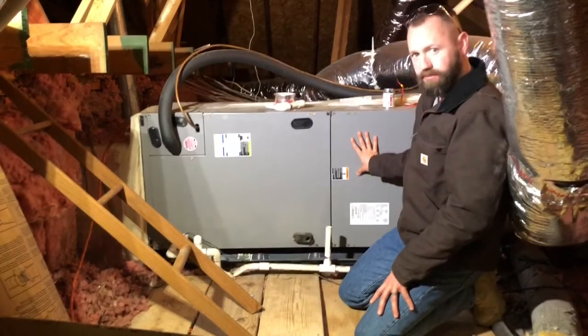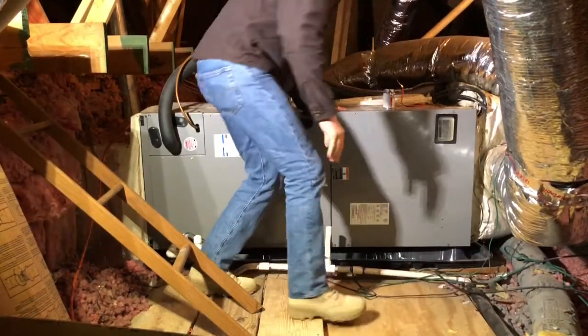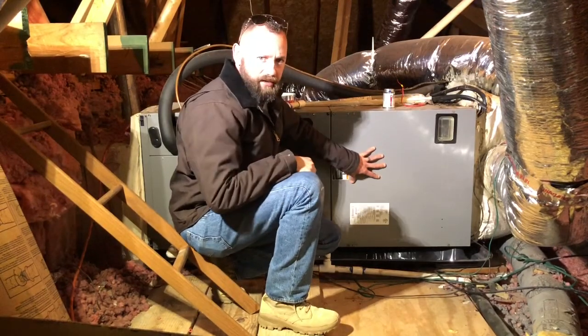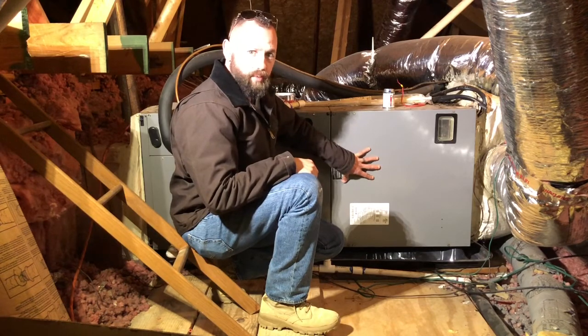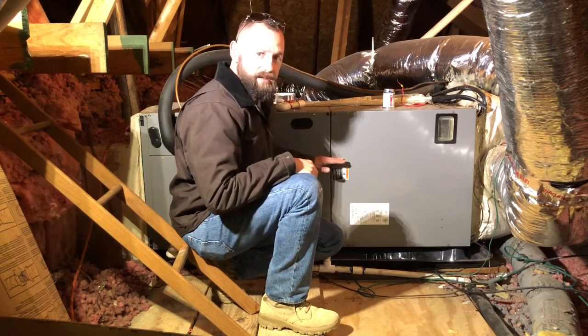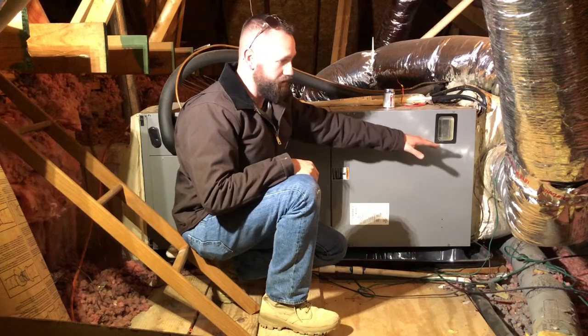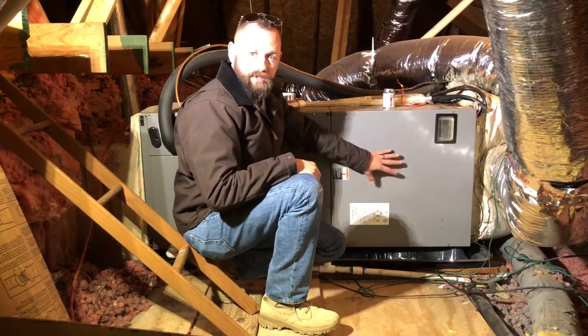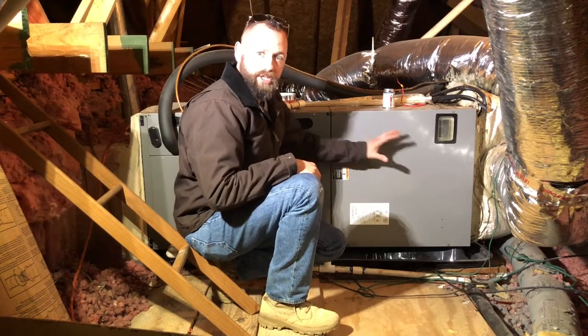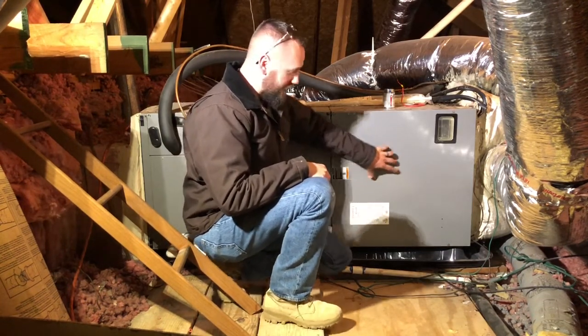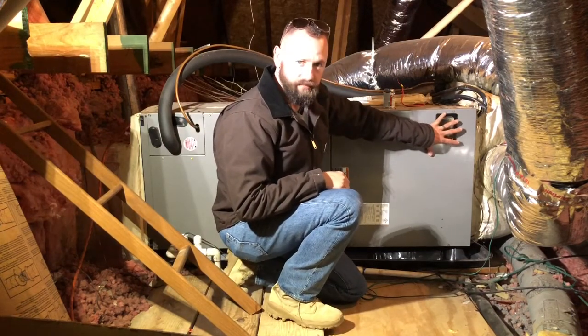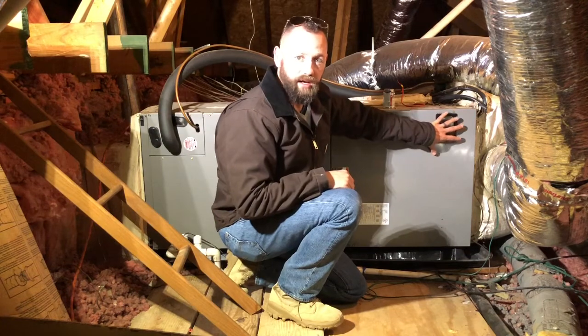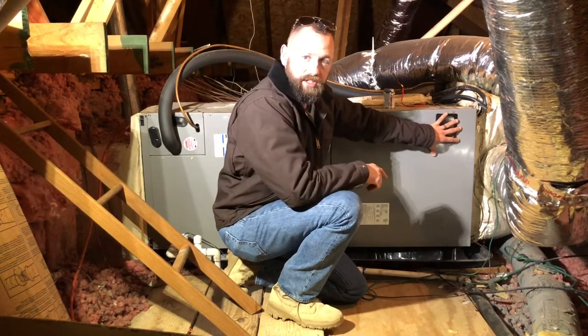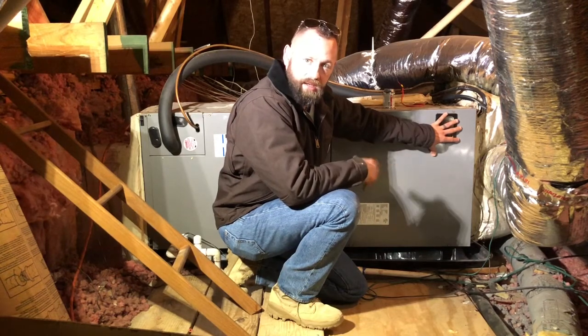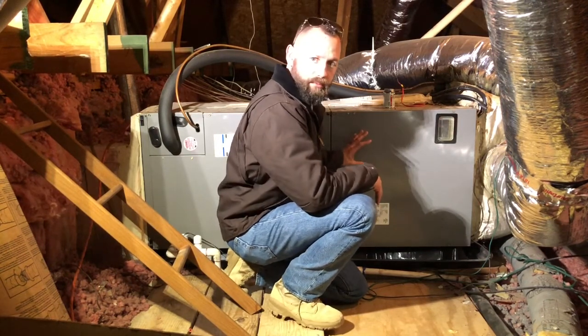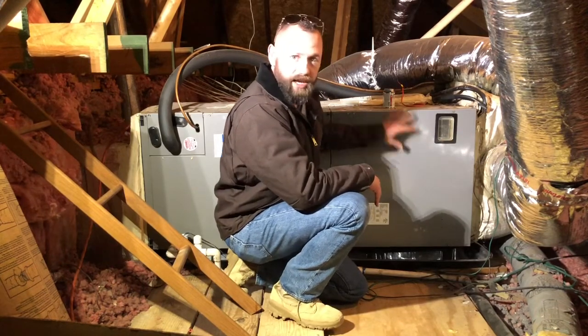Right here inside this compartment, and I'm going to move over. In this side of the air handler, we have a blower motor, which is what is sucking the air from the home into the unit and then forcing it back through the plenum and the ductwork back into your house. So it's pulling air up the return and pushing it through the supply. That blower motor's right here, and then at the very end you can see these breakers. This would be where your heat kit would be. So we've got electric heat on this air handler. So it's going to use heat strips that will glow and create heat when it's looking to heat the home, and that blower motor will push the air over the heat strips. So this is an air handler.